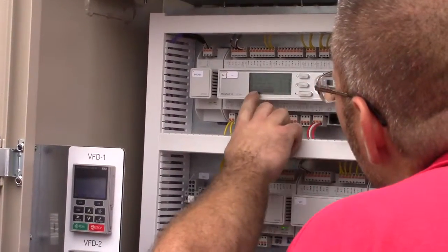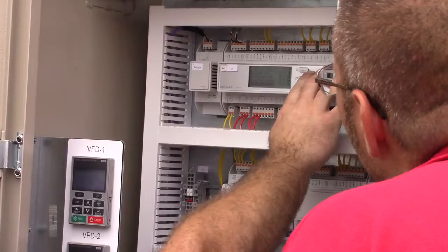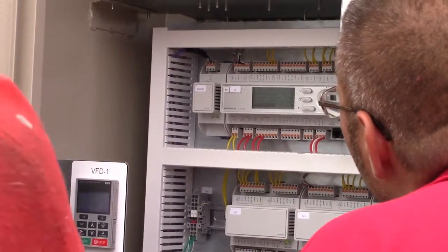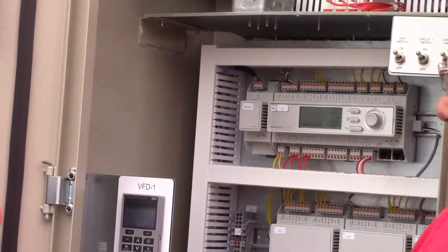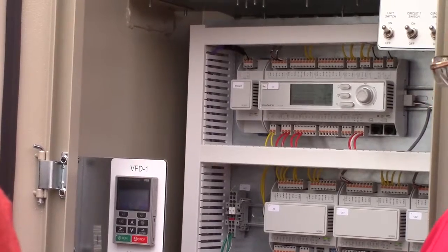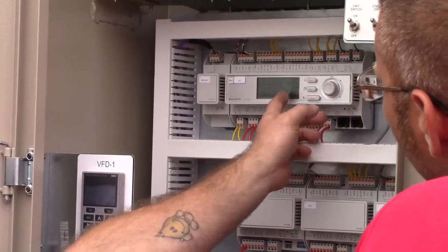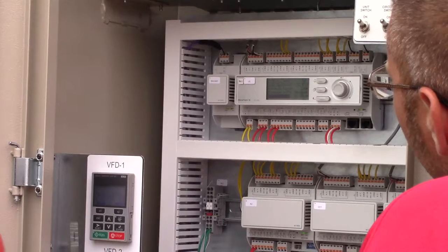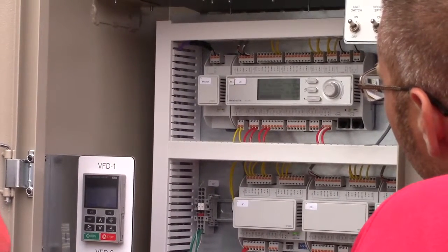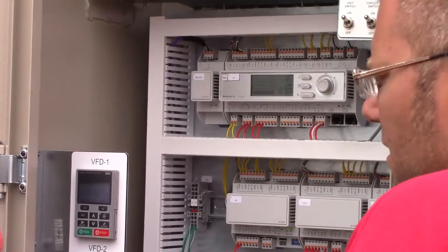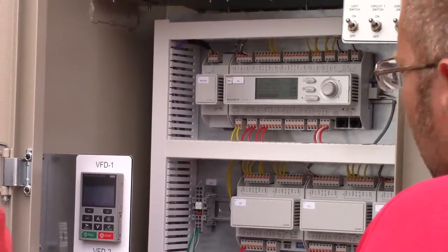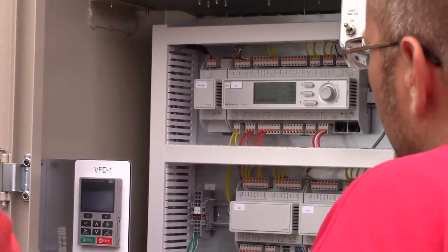Those are the two most critical points of operating the refrigerant circuit on these. And they'll give you other stuff like your evap approach and your condenser approach, that kind of thing. The other thing these do is they look at pressure ratio across the screw. Because we unload that screw with the drive, we are concerned about the lift or the pressure ratio across it. So we have valves in there that can maintain pressure ratio even at low speeds, just by blocking off the discharge ports to stack that pressure up. We used to not be able to unload a screw past like 24 hertz. Now we can go like 14, 12 because of that pressure ratio control.